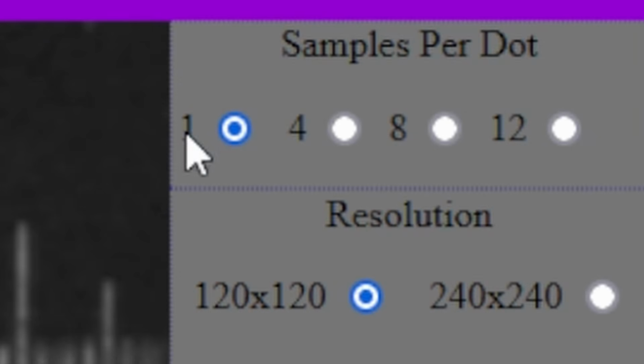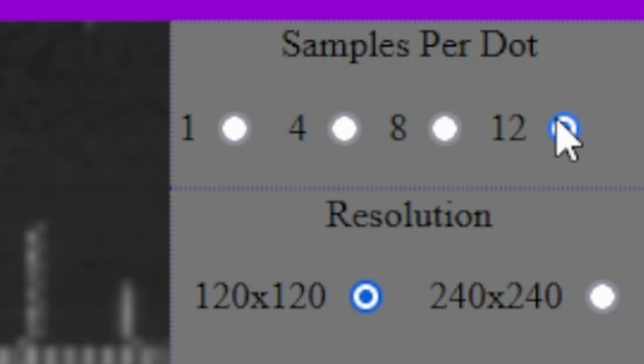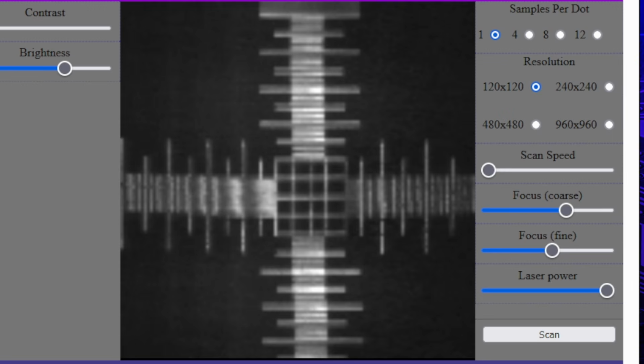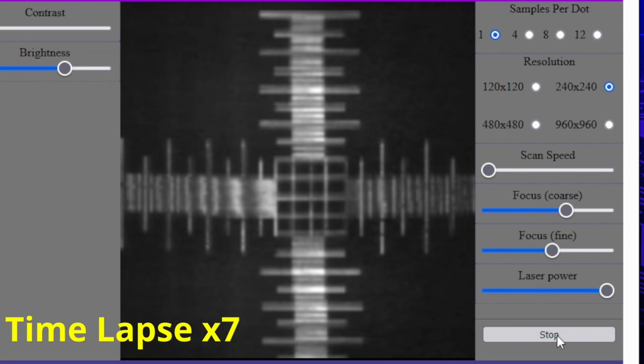You may also have noticed that the image looks a bit grainy. That's because of noise. I can select here whether to scan every point 1, 4, 8 or 12 times and make the average of these values. You see that the noise has become less, but scanning runs also slower now. The low resolutions are useful to quickly check the positioning of the sample. This first scan looks promising, so we can switch to a higher resolution and start over again.